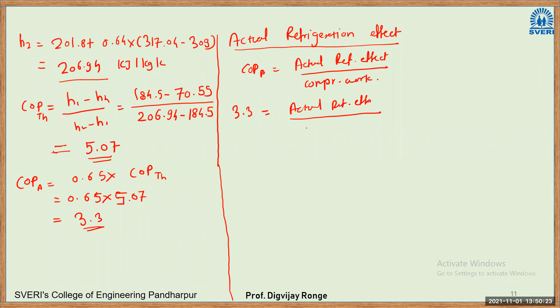So here it will be 3.3 equal to actual refrigeration effect divided by compressor work, which is H2 minus H1. So this will be equal to actual refrigeration effect divided by H2, which is 206.94 minus 184.5, equal to 3.3. So calculate the actual refrigeration effect. This is in kilojoule per kg, right? So calculate the actual refrigeration effect.